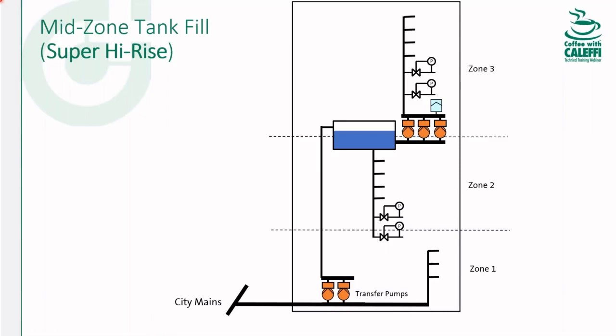Giddy up. All right. Okay, so last but not least, the super high-rise design. When the building gets to be so tall, at some point it's just impractical to have a ground-level pump boost all the way to the top. The pressure is so high, you're going to be in custom, non-standard designs for the pumps, and that's just higher costs and longer lead times, and you can't find service parts and all that kind of stuff. So this design has a storage tank mid-level in the building. And so the city mains comes in, the transfer pumps, just like in the last example, boost and fill that tank.